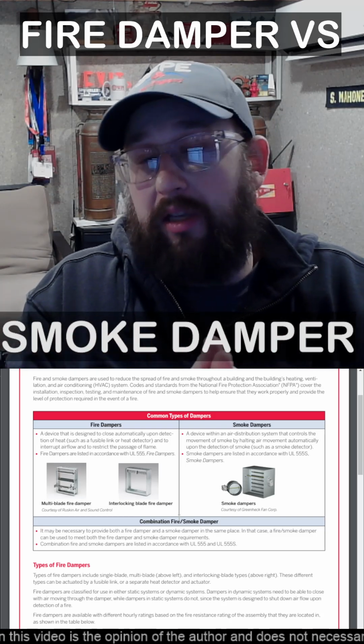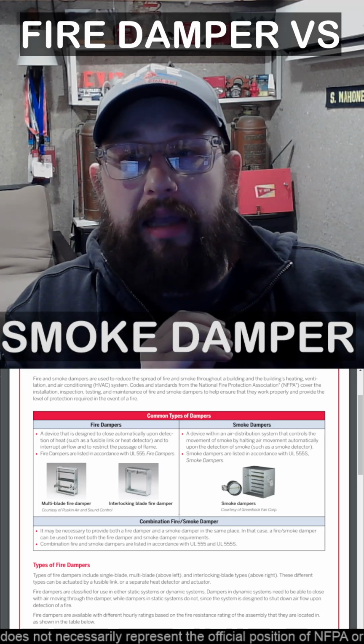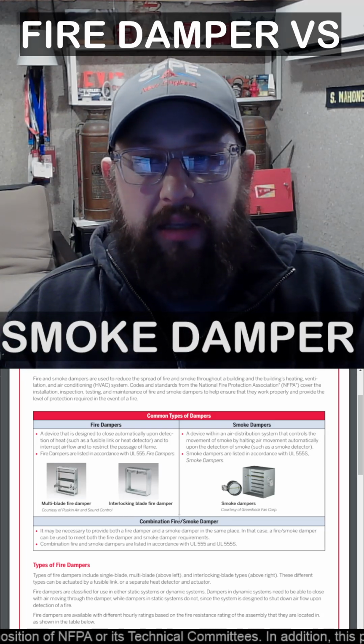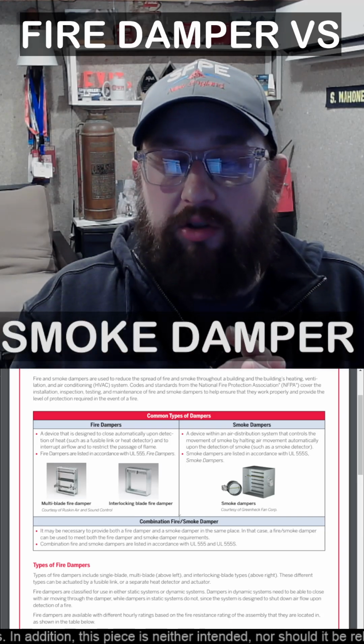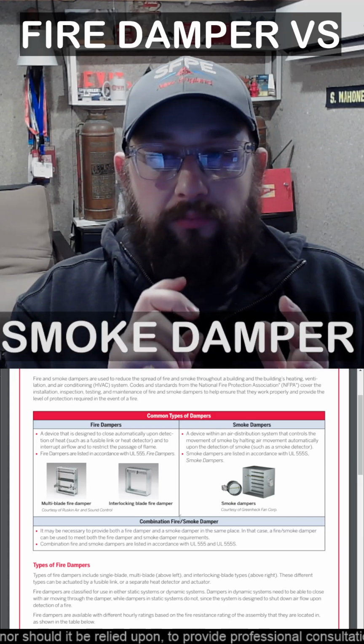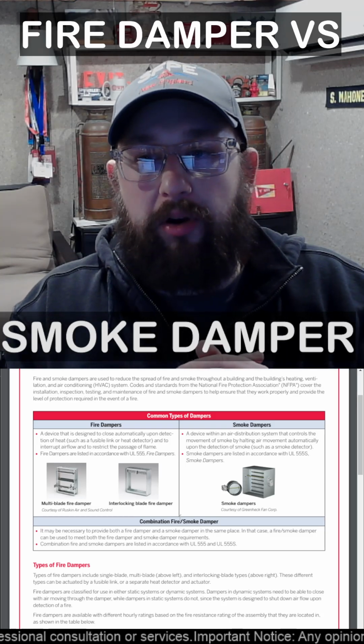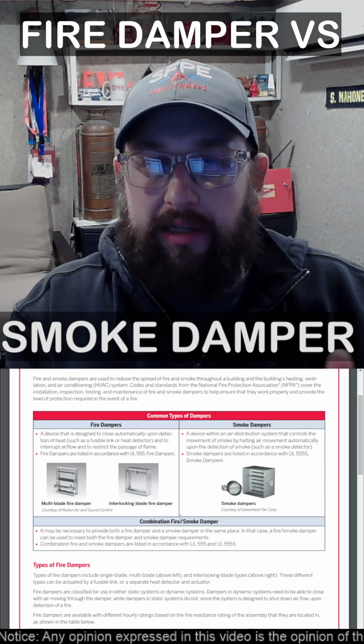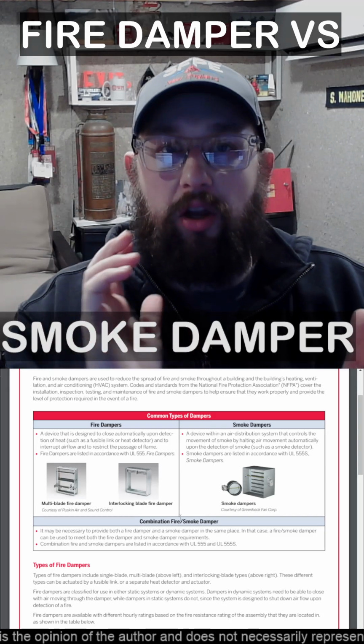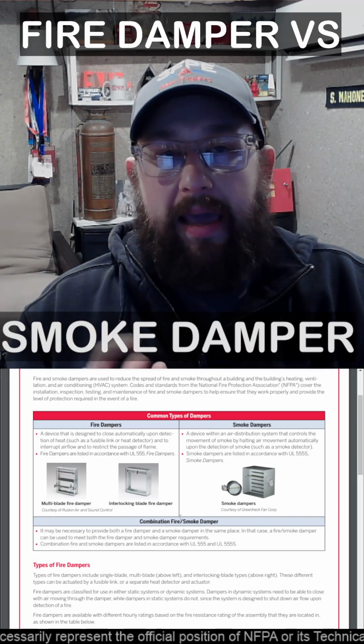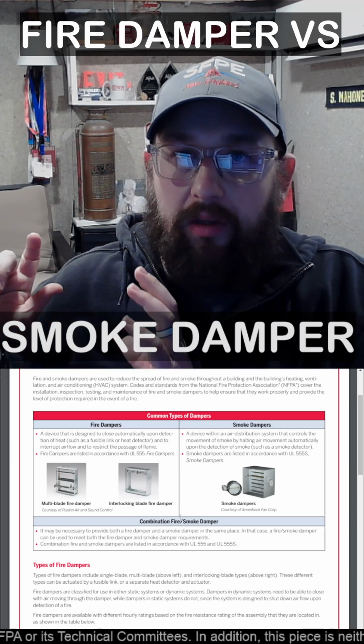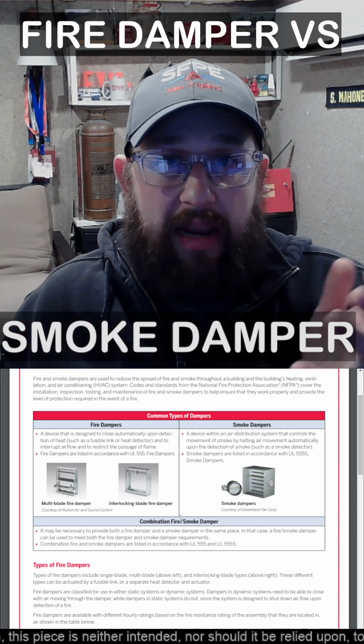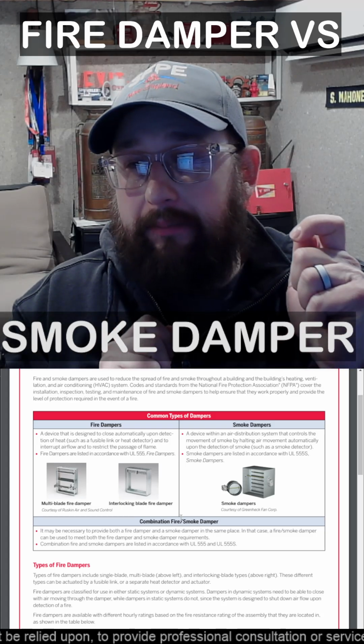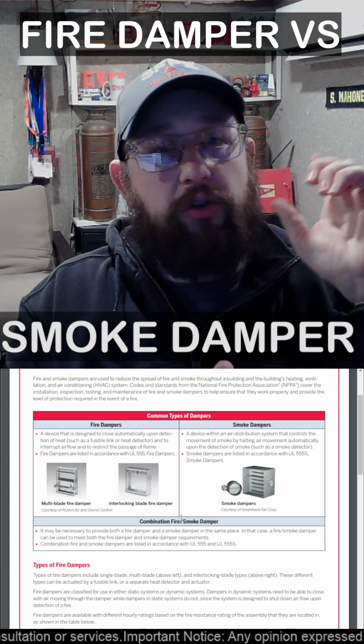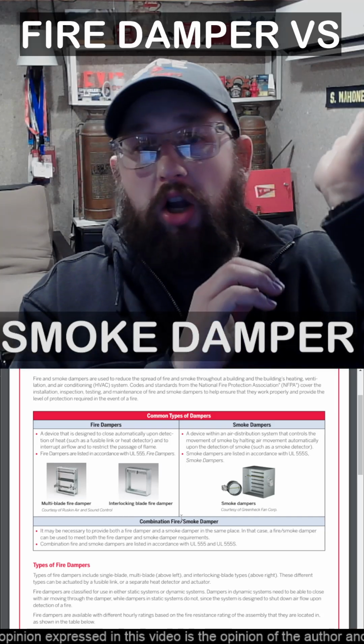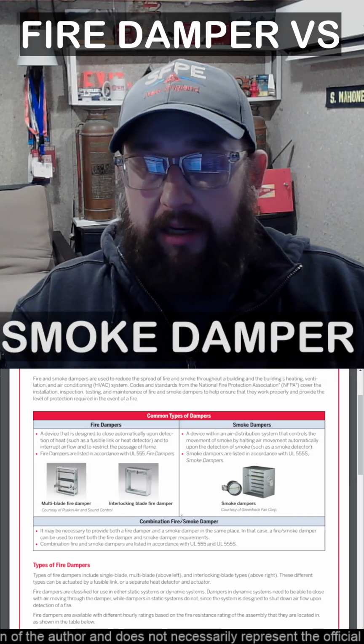So fire dampers can be two types. You can have actuated and non-actuated. Actuated means we've got an electronic solenoid that's going to open and close that fire damper, and we're going to rely on a heat detector or something like that and the fire alarm to trigger that. Or a non-actuated one's going to have a fusible link in it, and the fusible link's going to fuse, and it's going to cause that damper to just shut and latch.